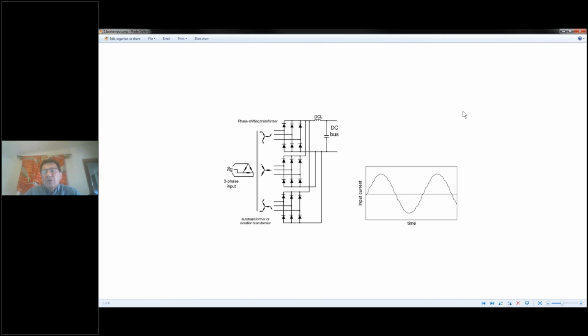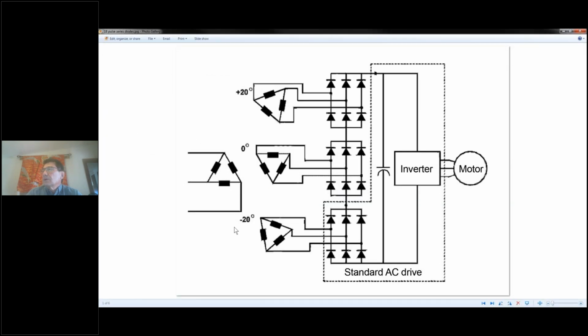This can get you into a lot of trouble when you go to retrofit and your diode bridges are not configured properly. It'll end up costing you quite a lot of money if you discover it at the site. So here, for example, is an 18 pulse series diode bridge setup, where this is the negative rail of the DC bus, this is the positive rail of the DC bus. I hope you can see my cursor, and you can see that the diode bridges are in series across the full span of the DC bus.